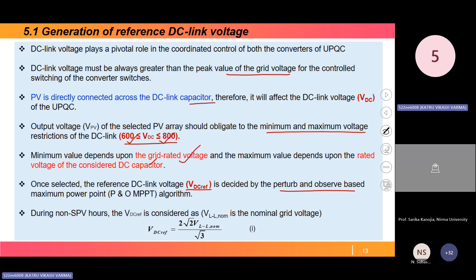But when PV is not there, or during non-SPV hours, the DC link voltage reference is to be set by this equation, where V line-to-line norm is the line-to-line voltage, times √2 by √3, into 2. So in this way, when PV is not there, you have to set this. When PV is there, you have to set a VDC reference between 600 and 800. These are regarding the generation of the reference DC link voltage, the first step.